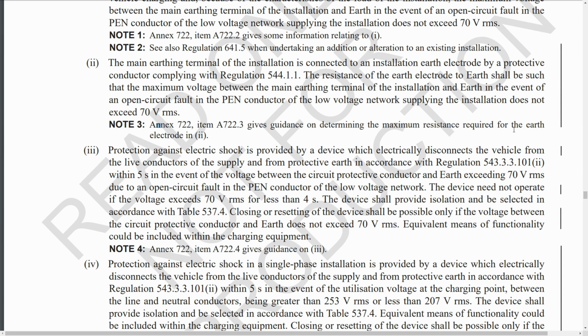In reality, you're looking at a resistance there in the order of 2 ohms or something like that, which you're simply not going to get with a single electrode or even a whole pile of electrodes in. The only practical application for this would be if you're putting one in, say, a domestic environment, the customer is having the entire driveway dug up and replaced, and as part of doing that, they're going to have a big mesh put under the driveway, so the sort of thing like in reinforced concrete or something, and that is going to be used as the electrode.